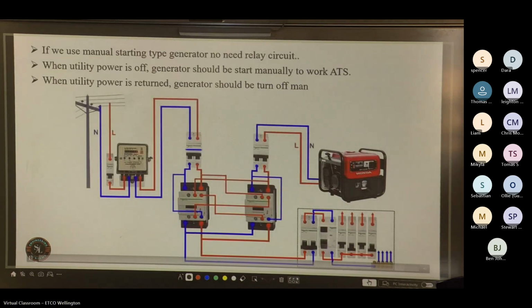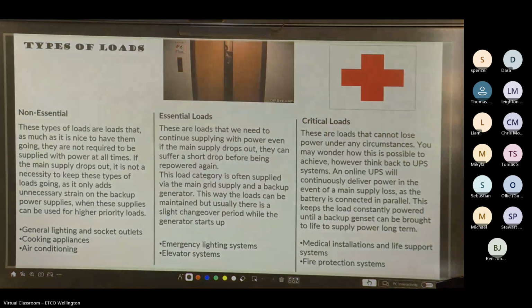Yeah, so it only works for the electric startup generators. So yeah, that's the way you normally would set up a generator like that. Obviously, if you were using a manual setup because yours is a plug-in, you'd still have to have either a changeover switch or contactor setup just to ensure that if you have the generator running and all of a sudden the main supply is brought back on, it will interrupt the generator supply. So that way you're not backfeeding the network.